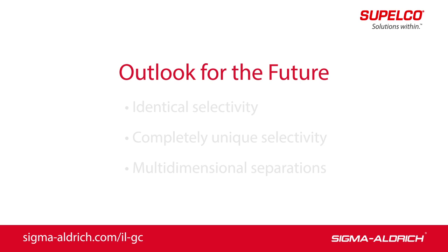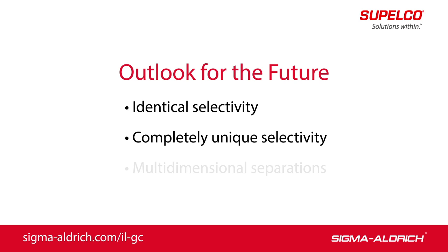Ionic liquid GC columns have the opportunity to impact current practices along several paths. Columns can be engineered with identical selectivity to non-ionic liquid columns, but with higher operating temperatures and less susceptibility to damage from moisture and or oxygen. Columns can be engineered with completely unique selectivity to non-ionic liquid columns, producing good peak shape and resolution for compounds of varying functionality. Columns can be used in multi-dimensional separations because of their engineered orthogonality and high thermal stability.